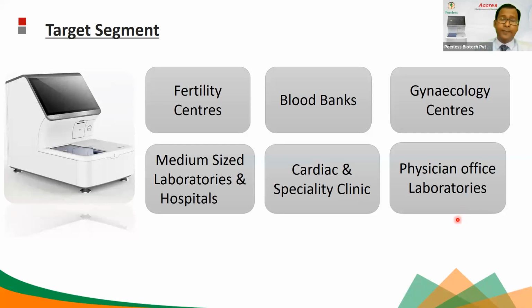Another big place, which I have not written here, is as a backup machine for big analyzers. In big labs, though they may have Maglumi, Siemens, or Abbott, for vitamin D and vitamin B12 the workload is not very high, so what happens? They cannot buy the kit and keep it, because the open vial stability of the normal CLIA is 30 days or 45 days. After 45 days, they have to throw the kit away. They cannot use it once again, right? So for such cases, they can go for a backup machine for vitamin B12, vitamin D, PCT. For parameters where the workload is not so much, they can take Accrea as a backup machine. That can be a beautiful place to work because they are generally high workload customers.